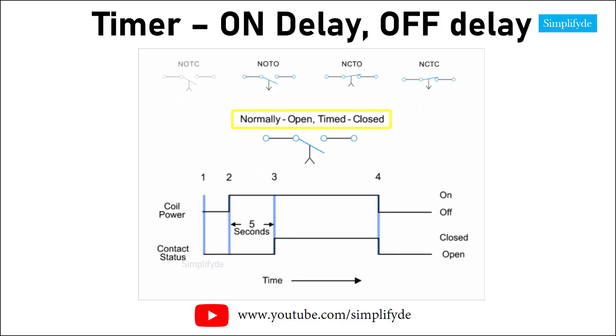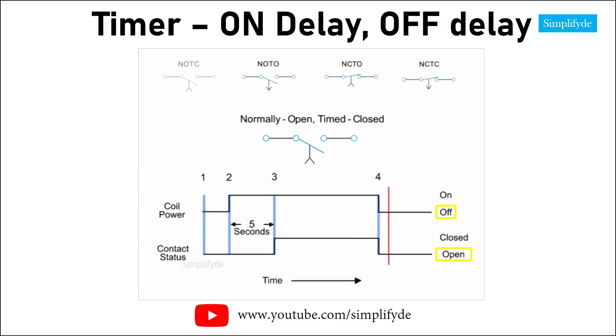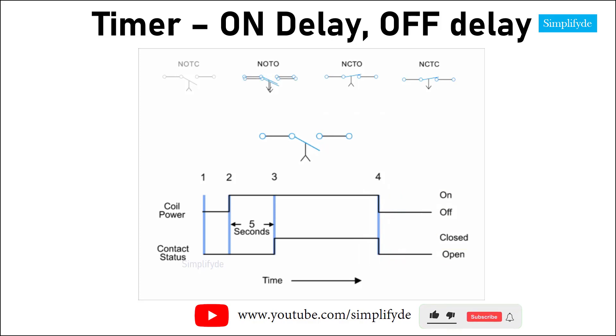First, we have the normally open timed closed (NOTC) contact. This type of contact is normally open when the coil is unpowered or de-energized. After the coil has been continuously powered for a specified amount of time — in this example, five seconds — the contact is closed. The contacts will immediately open when the coil is de-energized.